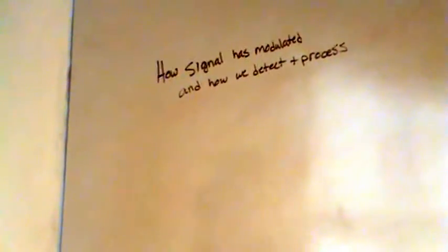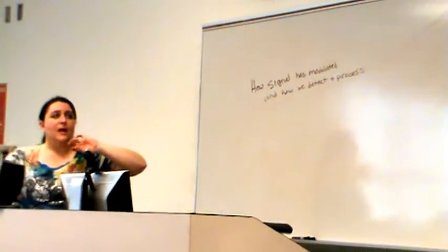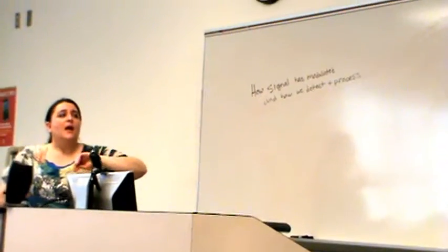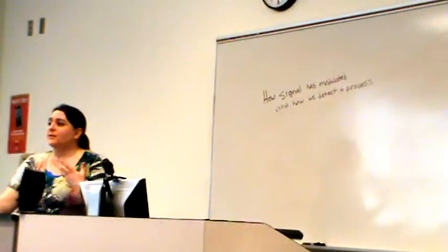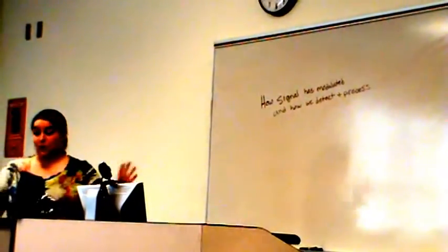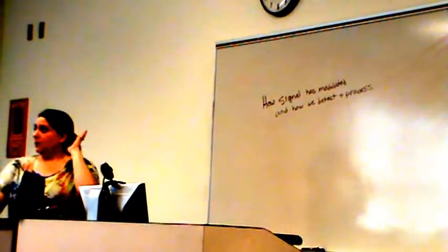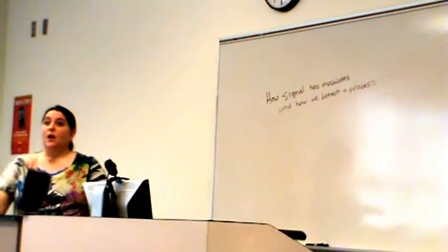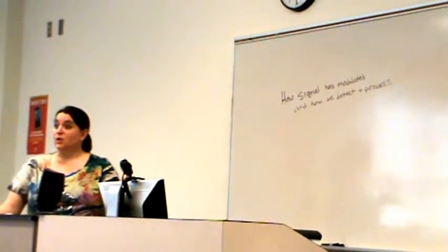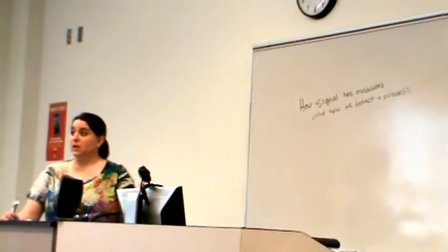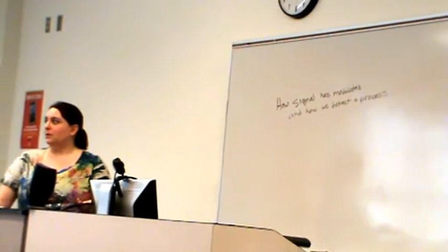It's been modulated. When we say something has been modulated, it just means that it's been changed. So we sent an ultrasound wave into the body. It had a particular frequency, a particular amplitude, wavelength, all that, and what we get back out of the body is going to be different. When we're talking about straight imaging, creating a 2D grayscale image, the frequency hasn't changed. That's not what changed in our case. The frequency and wavelength didn't change, but what changed was the amplitude, right?